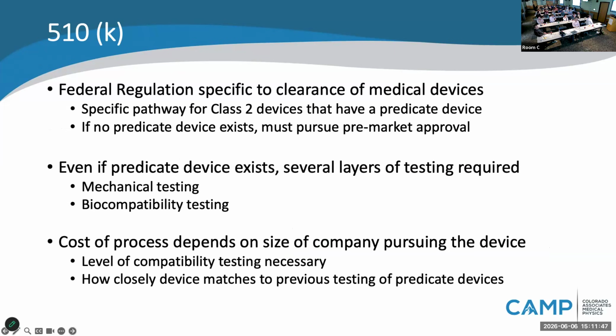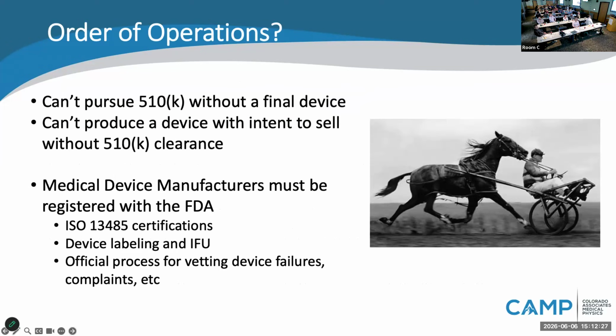So the 510K pathway, that's essentially where we are currently. Essentially you want to try to find similar devices that have already gone through some testing so you can say we don't need to go through the whole rigmarole of proving that it's safe top to bottom. It requires mechanical testing, biocompatibility testing. The cost of it, again, can be highly variable. You have to essentially predict what the FDA is going to take issue with and then try to remedy that up front and limit the number of back and forth communications between them. And this is where we're still trying to figure this out. So if anybody in the room knows, then come talk to me afterwards.